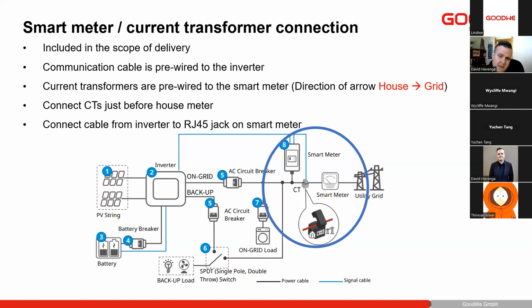Please never use extenders to extend the cable. Take that cable out, put a new cable in, and you can put it up to 100 meters away from the inverter. You can install up to 100-meter long cable. Make sure it's a nice insulated cable, so Cat 6 or Cat 5e insulated network cable, and then you can run that about 100 meters away from the inverter.